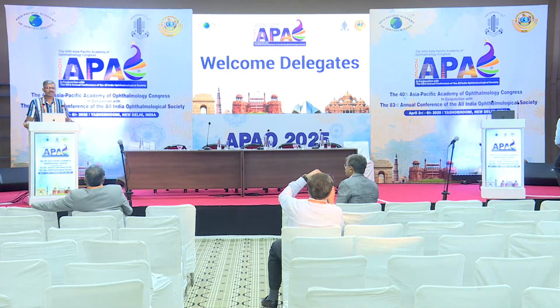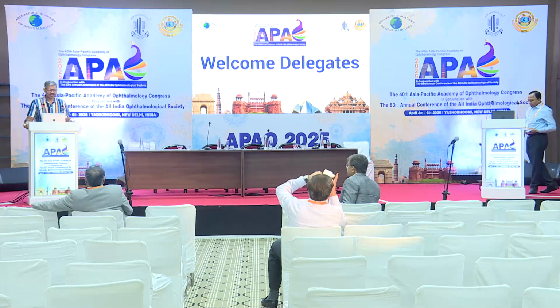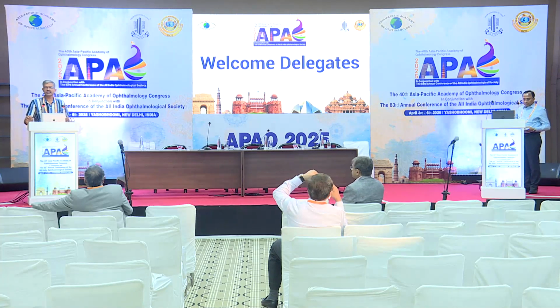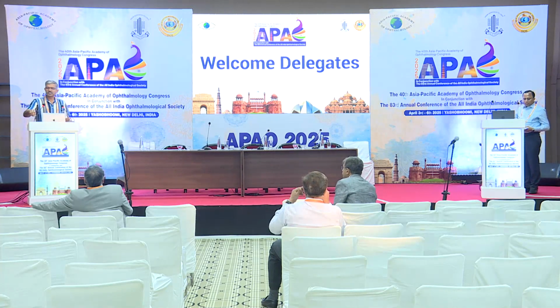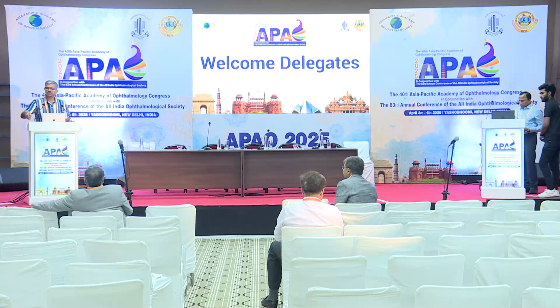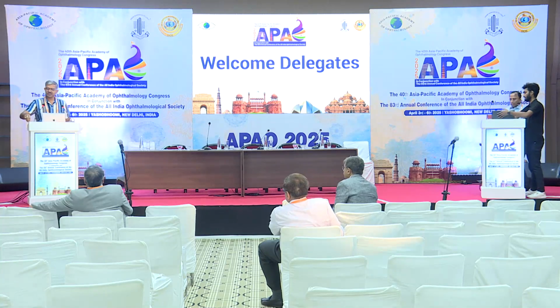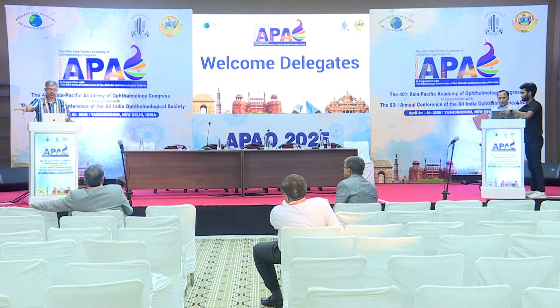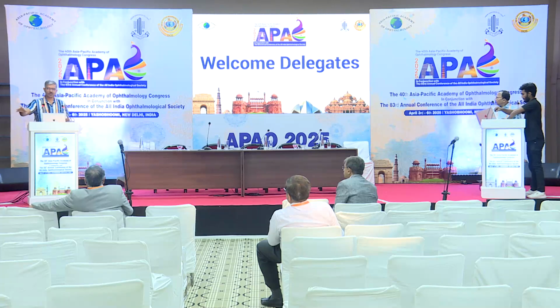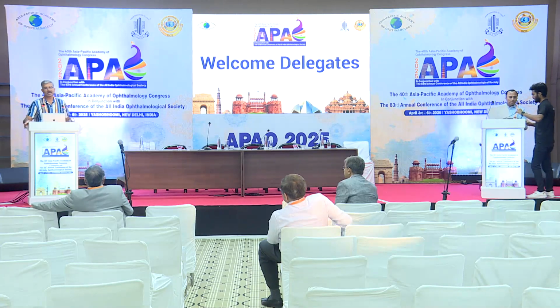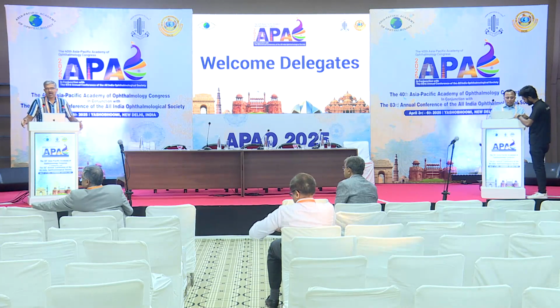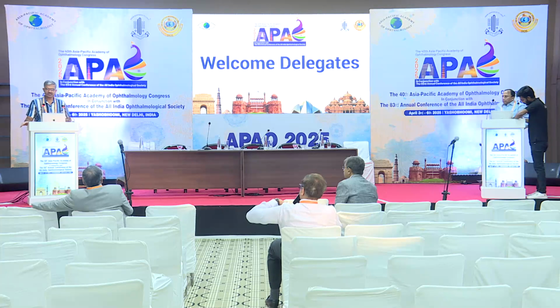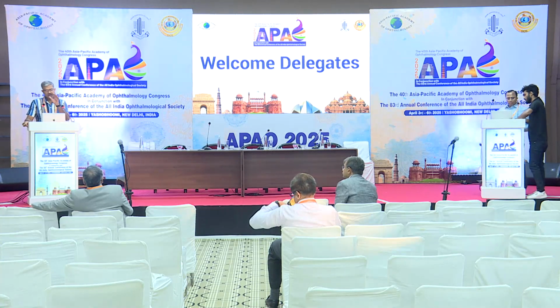What Rayner claims is, by changing the order, and I was trying to understand from their patent papers, they've actually done some good work. The only thing that needs to be seen is, despite the orders being changed to -1, 0 and +1, the distant focus still stays at the 0 order focus. So that's still the brightest spot, and that's still the point where the chromatic aberrations are happening. So how far they have addressed this is something that we still don't understand very well. But echelette in the Symphony also is working. So that's what I'm saying.